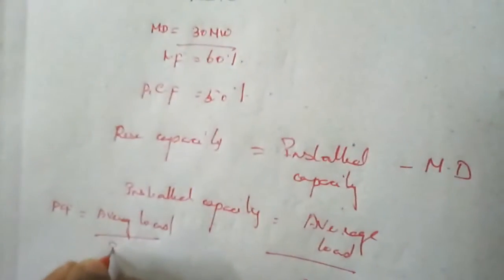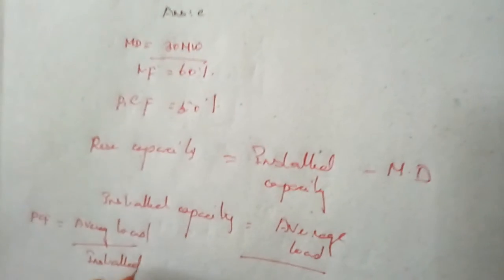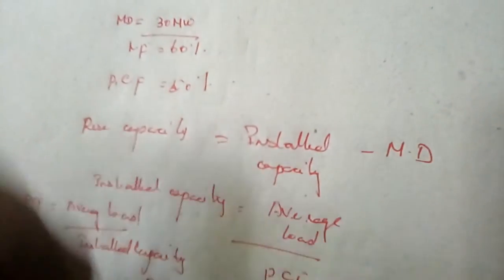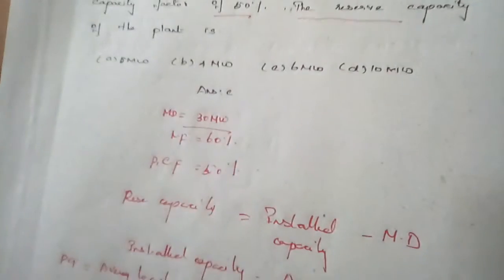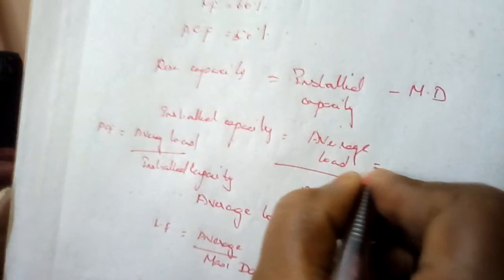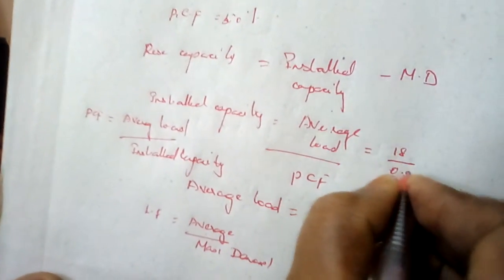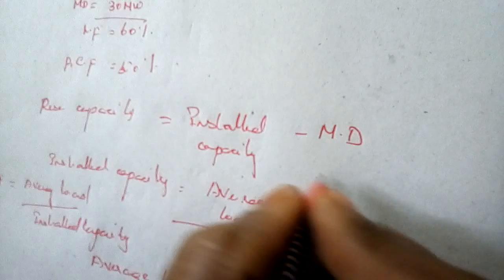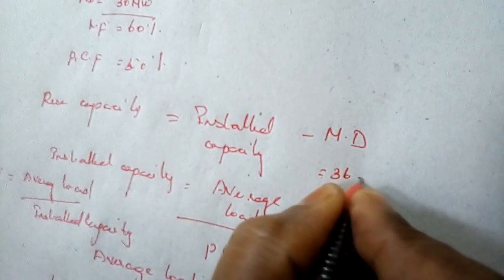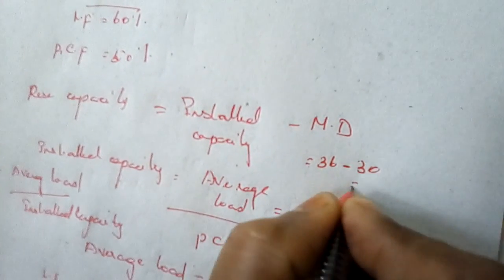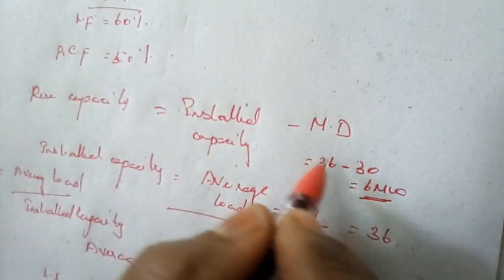The plant capacity factor is 50 percent (0.5), and the average load is 18 megawatt. So installed capacity equals 18 divided by 0.5, which equals 36 megawatt. Reserve capacity equals installed capacity minus maximum demand, which is 36 minus 30, giving 6 megawatt as the reserve capacity.